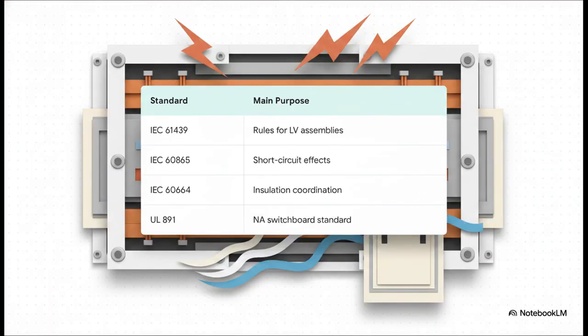Let's zoom back out to the macro level for a second. Designing a safe busbar system isn't just about applying pure engineering theory. It's all about adhering to rigorous international frameworks. We've got the IEC 61439 series for the switchgear assemblies themselves, IEC 60865 for short circuit calculations, and IEC 60664 for insulation coordination. Over in North America, UL 891 plays a very similar assembly-level role.